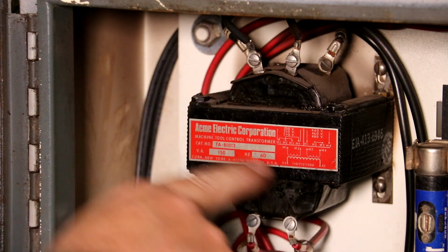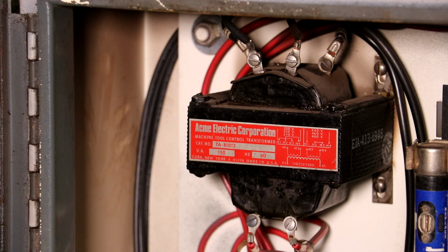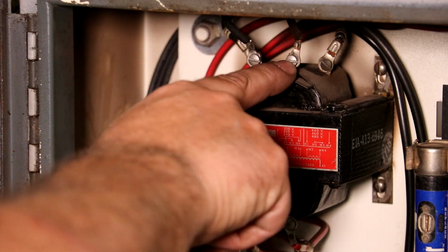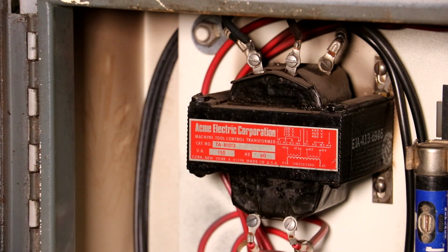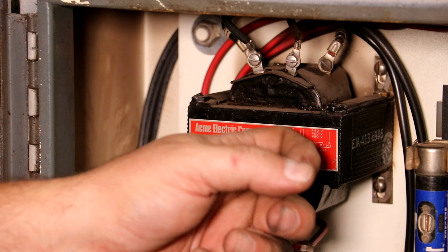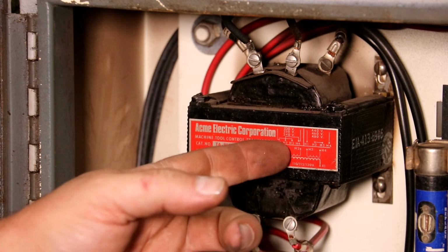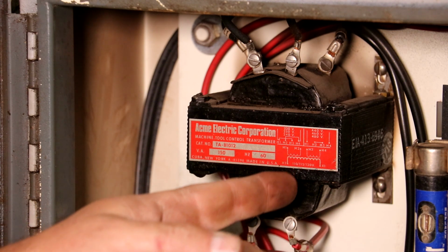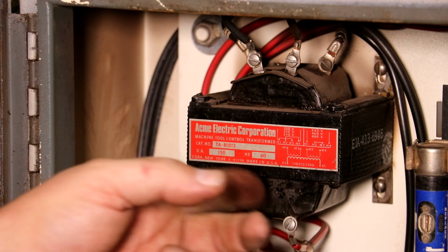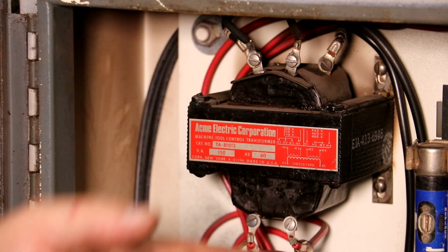It shows your line voltage coming in, the 2 on the outside, and then the 2 middle ones just connecting those 2 together. So to go to 220, we need to take this jumper here off. When you put a jumper between this input and this one, and this input and this one, that will change the windings inside this transformer to change the voltage. If I were to put 220 volts into this instead of 440, out the bottom, instead of having 110 or 120 volts, it would give me half that - about 60 volts. I need to get 110 or 120 volts out of the bottom, depending on the input voltage.